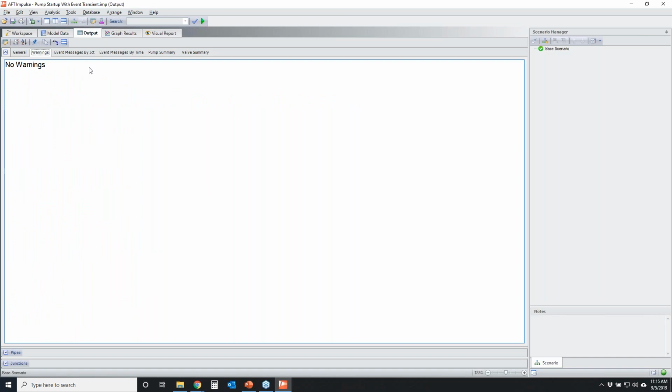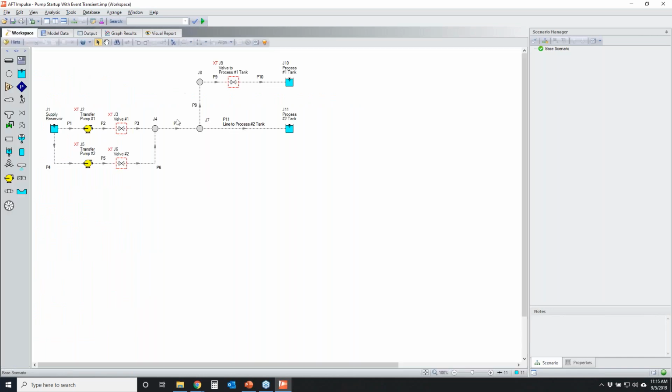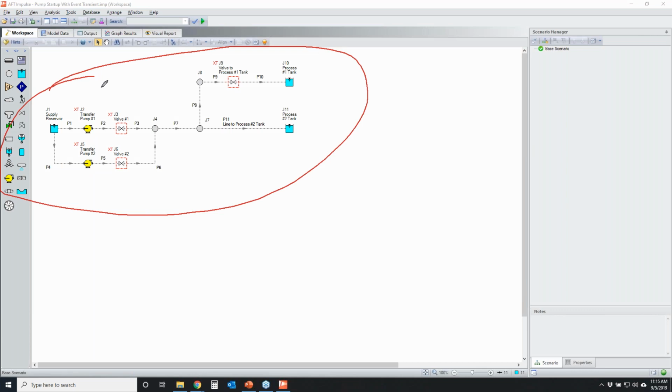But here's the thing. Do you really need to use variable resistance all the time? Well, cases where that's important is like this, where if you have no flow initially in your system, or maybe you have parts of your system that are initially closed off to flow, and then later in your analysis, you're allowing them to open up. This is where you'd want your friction factors to be able to change.